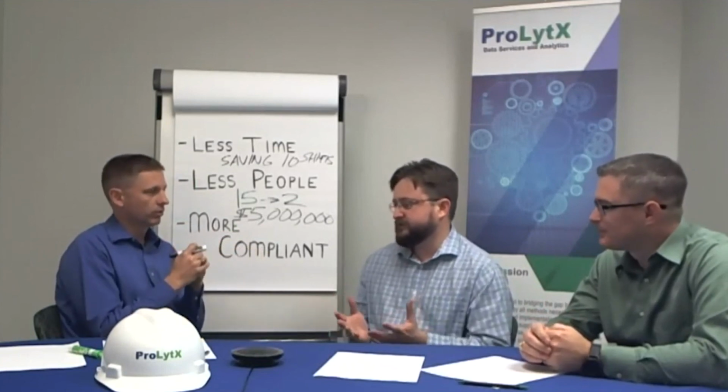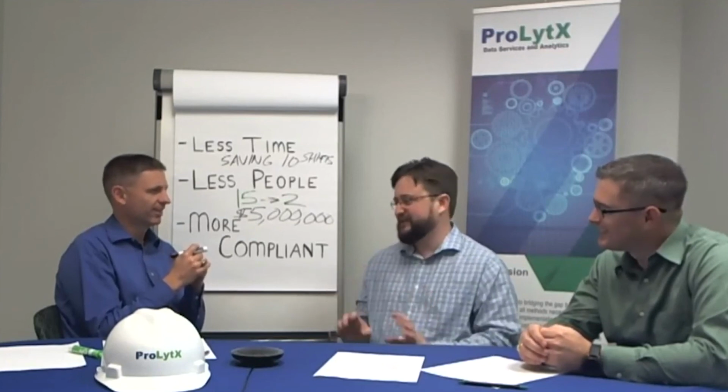And over the last few years, we've done over 150 different SIS platforms and different processors. And I can easily say that not a single one of those has gone by without us finding something. These are systems, in most cases, that are already in service, and we're finding issues. Were any of those systems ones you originally did? Those were not ones I originally did. No. Okay.